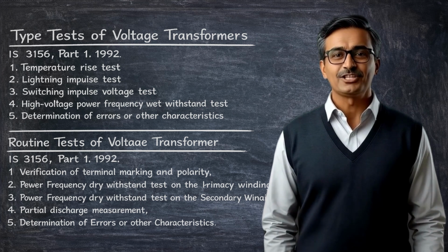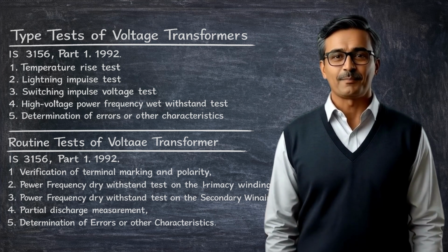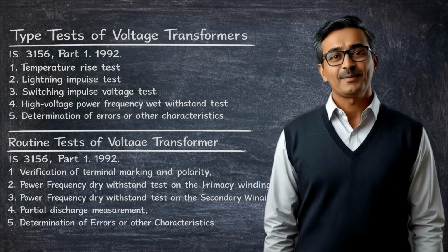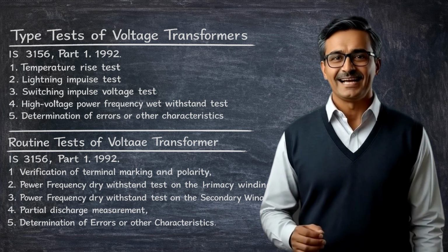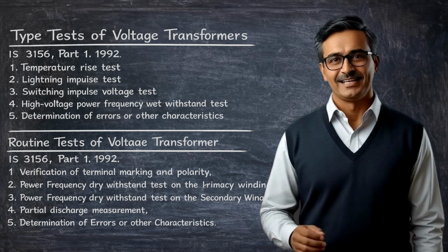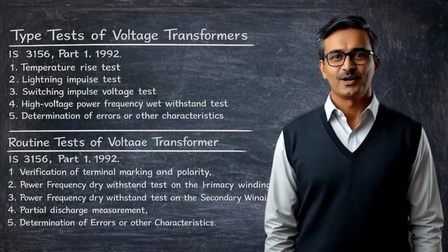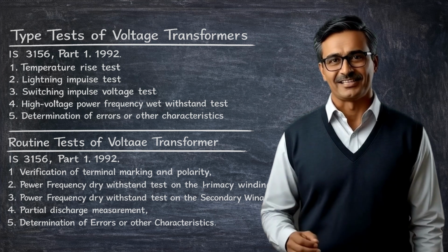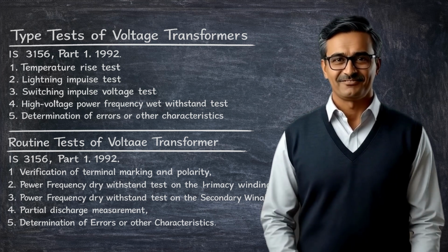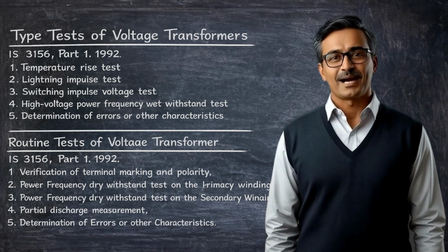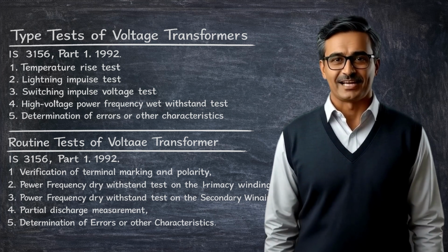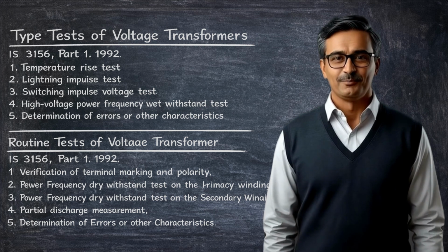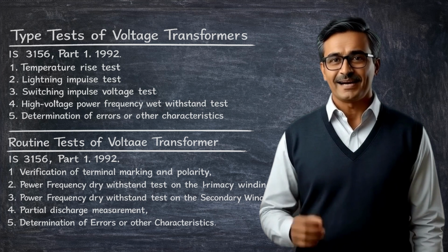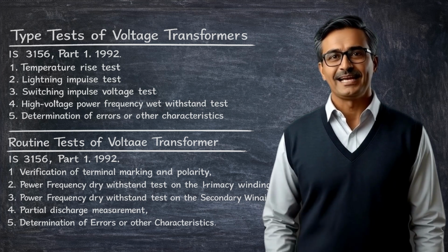Now let us look at some important notes regarding these tests. First, the determination of errors or characteristics must be carried out after completing the primary and secondary power frequency withstand tests. The sequence of the other tests or their combination is not strictly standardized. Another important note relates to repeated power frequency tests on the primary winding. If the power frequency withstand test on the primary winding needs to be repeated during acceptance tests, the test should be performed at 80% of the specified test voltage. This requirement helps prevent unnecessary stress on the insulation system.